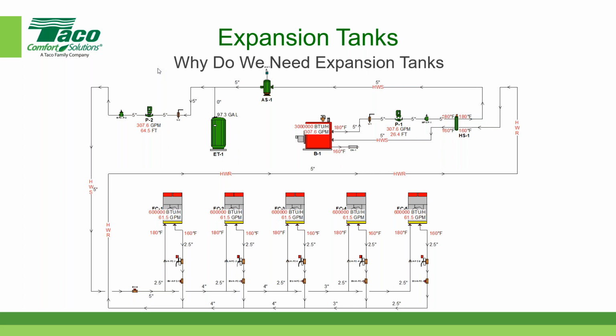Now, the good news is that if you use our HSS software, which Brett is going to demonstrate 2 weeks from tonight, then he will show you how the software will calculate the volume of water in the system. And in fact, I use the software, that's what's on the screen right now. That's how you can figure out what the volume is. For our calculation tonight, we calculated the volume to be approximately 2,000 gallons. That's what we used for our system volume, 2,000 gallons.